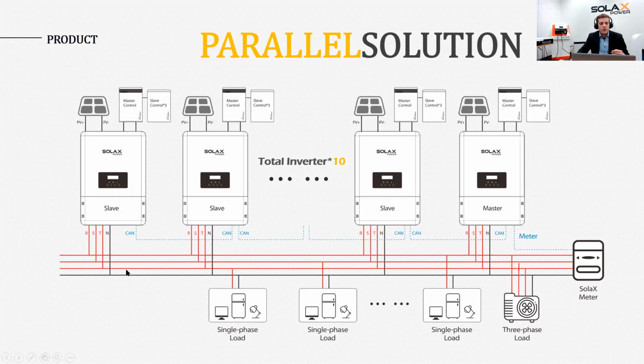What I really wanted to show you is the balanced and unbalanced mode. Imagine your inverter is producing 10 kilowatts. In balanced mode, it puts 3 kilowatts on every phase - splitting the energy into equal parts. In unbalanced mode, my favorite, it puts out exactly what's needed on every phase - so 6 kilowatts on the first phase, 1 on the second, and 2 on the third, exactly matching demand.